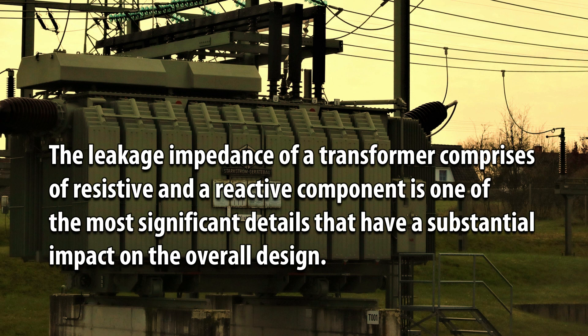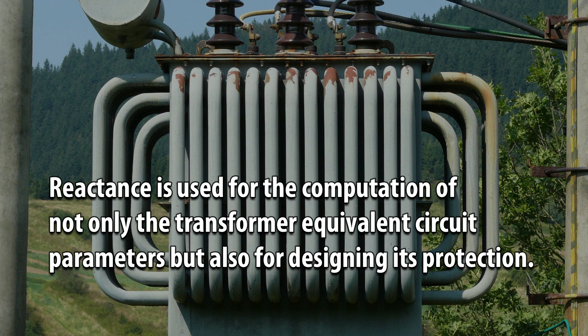The leakage impedance of a transformer, which comprises resistive and reactive components, is one of the most significant details that has a substantial impact on the overall design. The reactance of the transformer windings is an important component of the design with a direct effect on its operation. Reactance is used for the computation of not only the transformer equivalent circuit parameters but also for designing its protection.